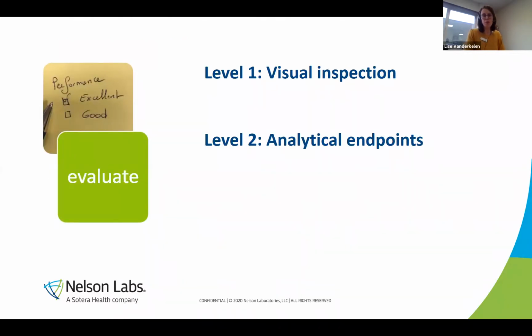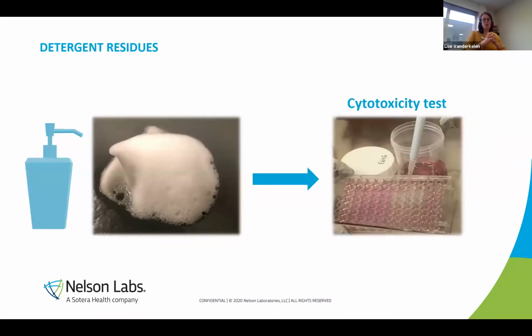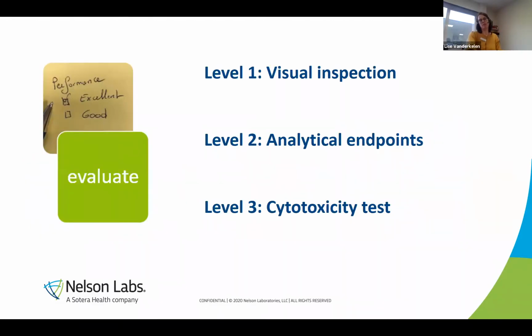That brings me to the 3rd level, detergent residue. The detergent residue is, as you can see, also important because it can also be harmful for the patient. For this testing, we're not going to clean the device with worst case cleaning parameters from a soil residue point of view, but here we're going to take 3 other devices and clean them with a high amount of detergents, like the highest in the range of your IFU. And we're going to reduce some rinsing step and see whether or not, in this extreme situation, we see detergent residues, and we will evaluate it by using a cytotoxicity test. So that is level 3, the cytotox test.